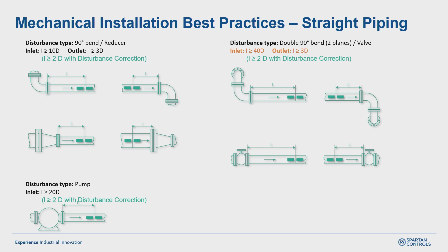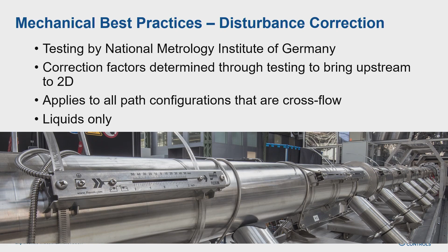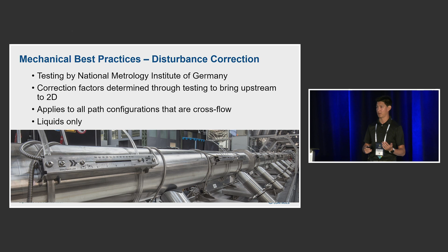Now, there is a software feature on Flexim units called disturbance correction. And basically, at the National Metrology Institute in Germany, they did a whole bunch of testing with a whole bunch of pipe disturbances. So we have a bunch of empirical data that says, hey, if we do not install this as per the straight piping requirements, we are still going to get X accuracy, which will be significantly better than what it would be out of the box.